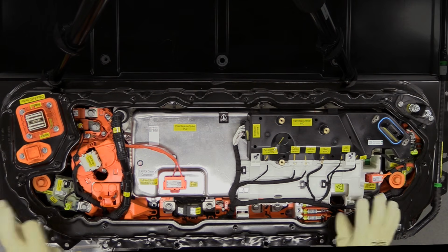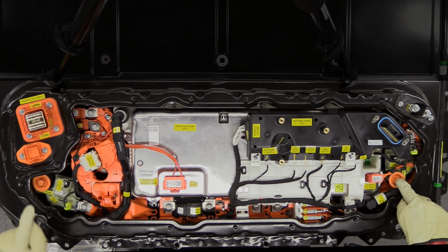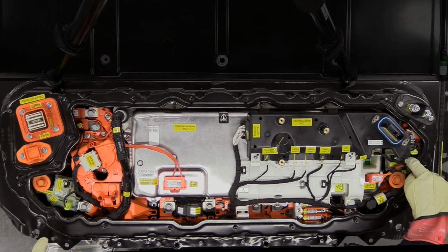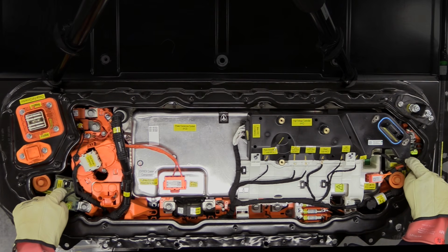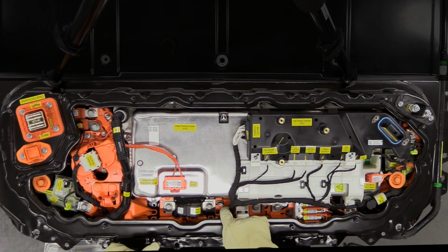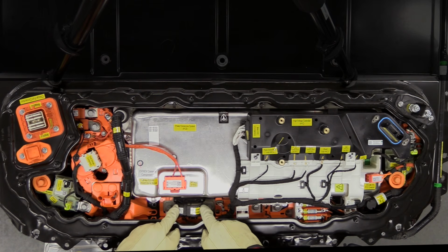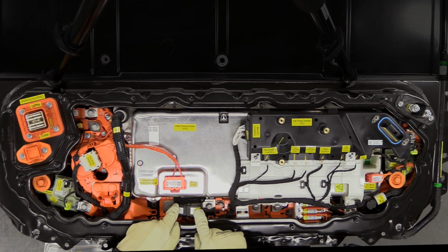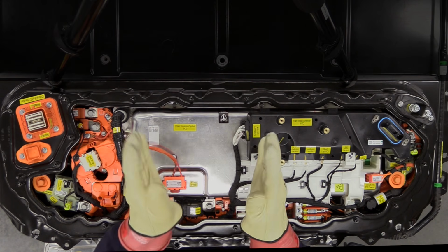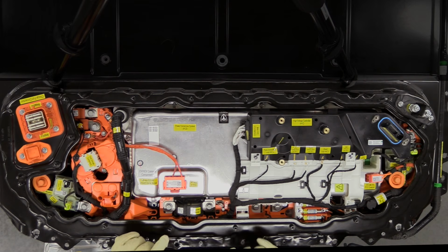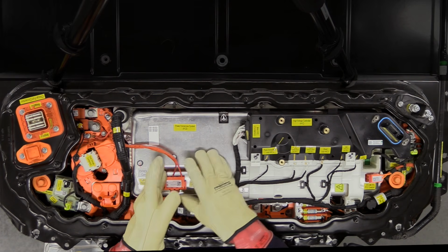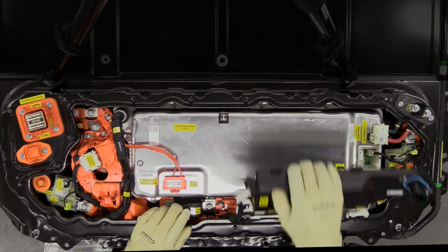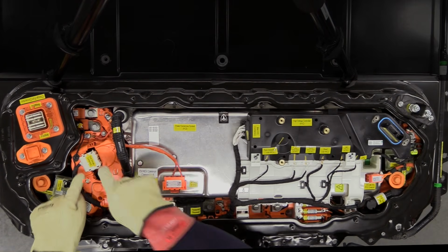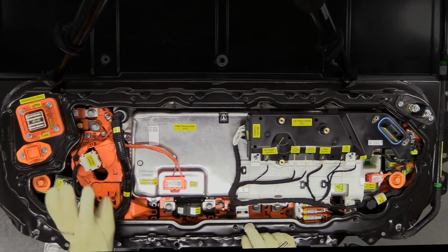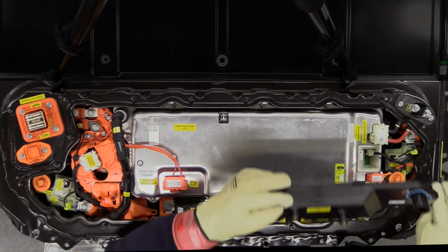So really, inside of this ancillary bay, we have the positive and negative terminals connected to the positive and negative contactors that connect to the current shunt. There's a pyrotechnic disconnect, almost like a fuse, except it's not a fuse. It just open circuits the whole battery when needed, that splits the battery right down the middle when necessary. And then we have the connection to the power conversion system. We have the high voltage controller, the additional contactors for the DC fast charge, and then our output.